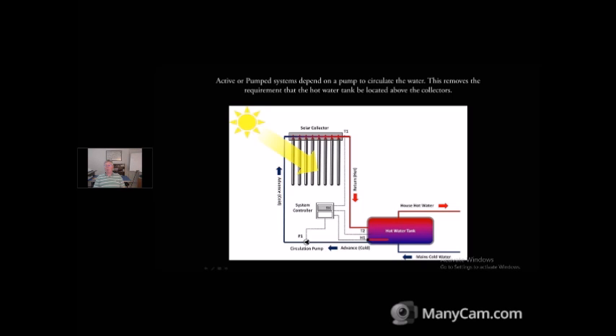You've got a pump, and of course you have to power that pump. It's typically powered electrically, so you take your solar PV or whatever and you would power that pump, and that actually circulates the water in and out. This particular diagram is again for a direct system because we're pulling water directly out of the hot water tank, running it through some collectors, and then returning it back hot.